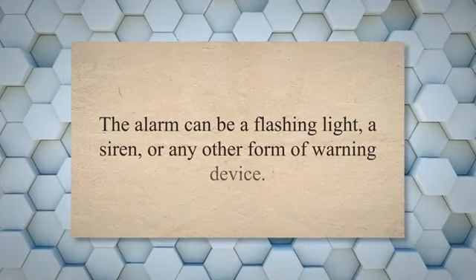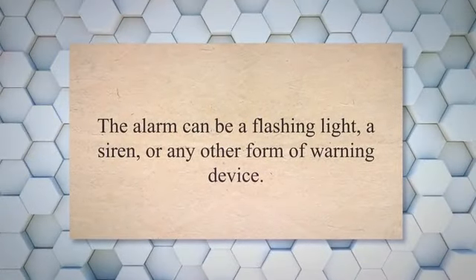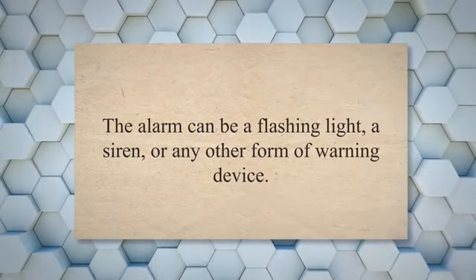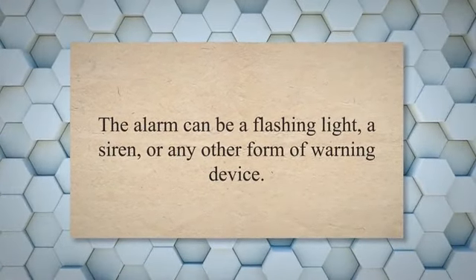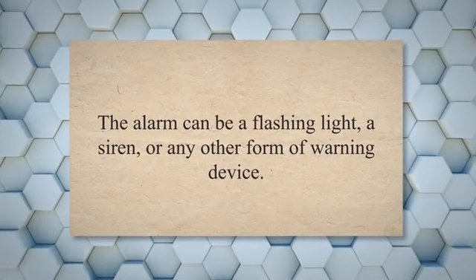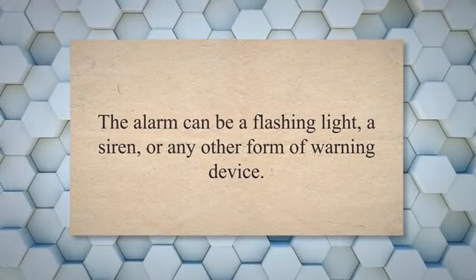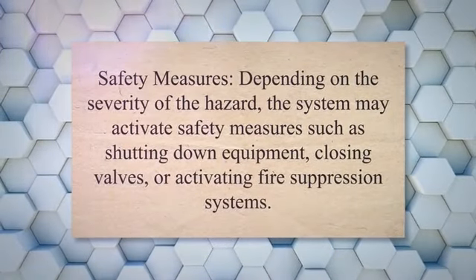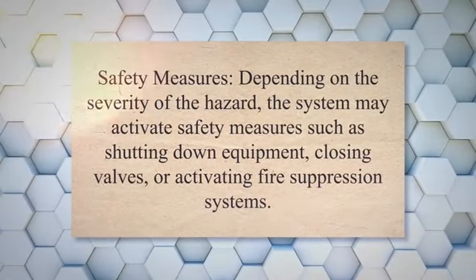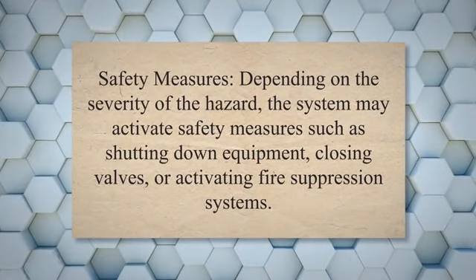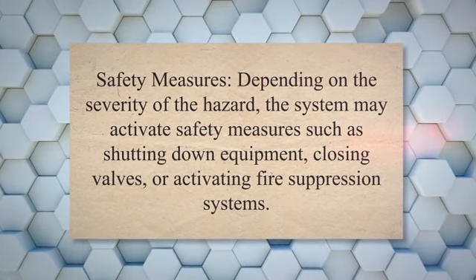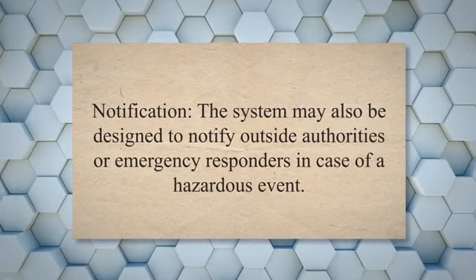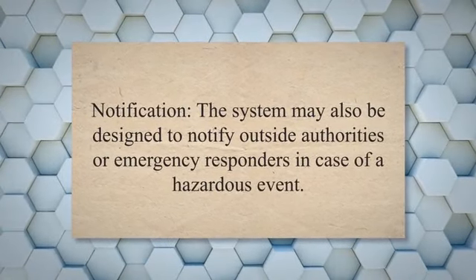Alarm activation. If the level of hazard exceeds a predetermined threshold, the control panel activates an audible or visual alarm to alert personnel to the potential danger. The alarm can be a flashing light, a siren, or any other form of warning device. Safety measures. Depending on the severity of the hazard, the system may activate safety measures such as shutting down equipment, closing valves, or activating fire suppression systems. Notification. The system may also be designed to notify outside authorities or emergency responders in case of a hazardous event.